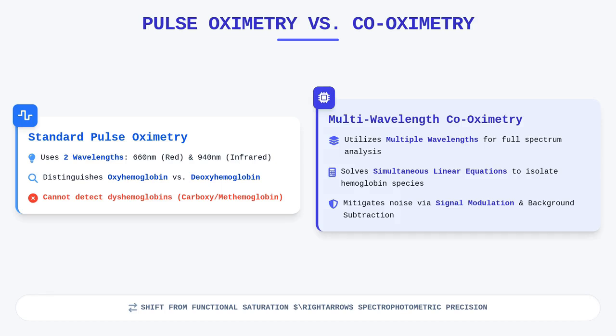Turning to oximetry, we must understand the shift from simple infrared pulse oximetry to multi-wavelength co-oximetry. Standard pulse oximeters operate by emitting two wavelengths of light, typically 660 nanometers for red and 940 nanometers for infrared, to distinguish between oxyhemoglobin and deoxyhemoglobin based on their distinct absorption spectra. While this suffices for identifying functional oxygen saturation, it cannot resolve the presence of dyshemoglobins like carboxyhemoglobin or methemoglobin.